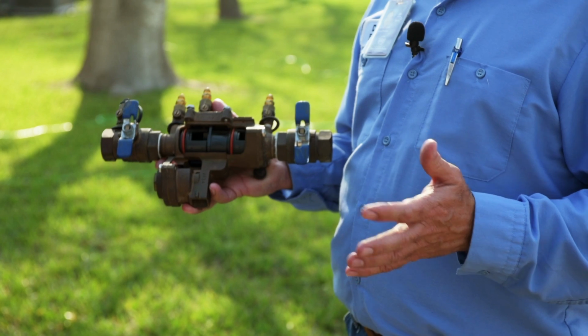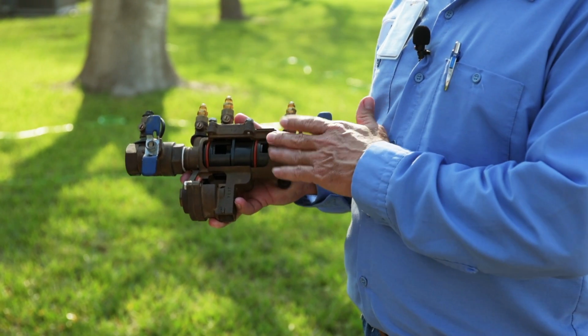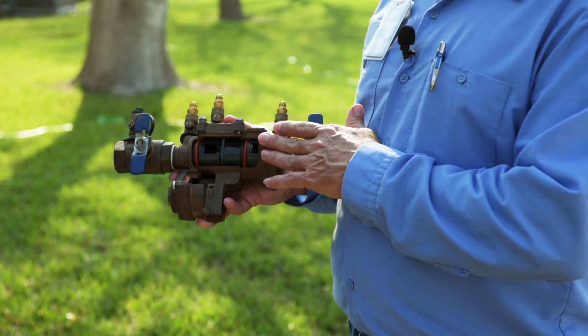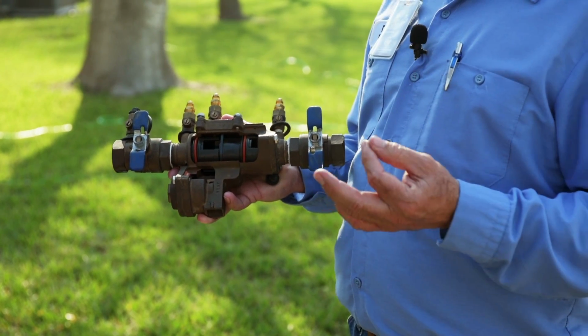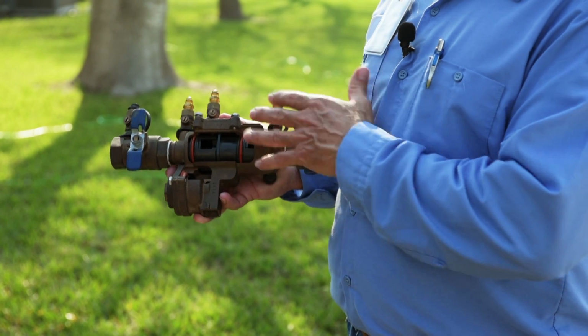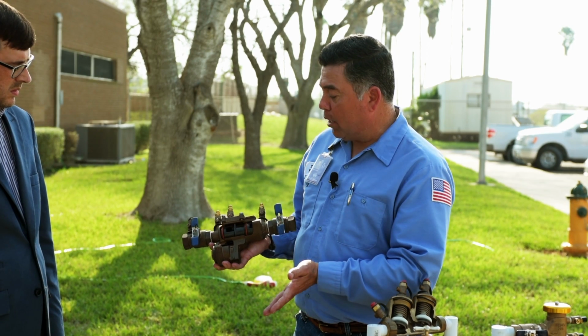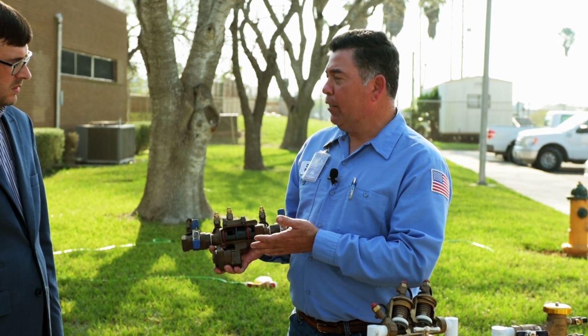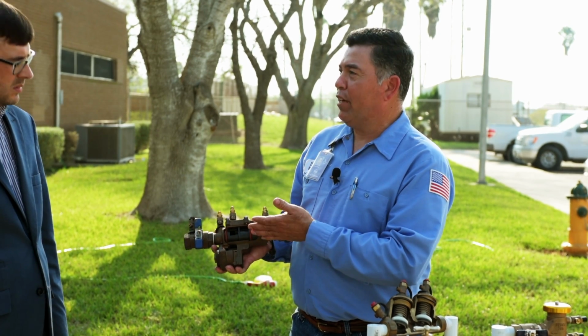This type of valve is used when a customer has auxiliary water on the property. That's basically resaca water or well water. We ask customers to install a testable backflow prevention assembly. Something like this with 2 check valves, and it's got a relief valve on the bottom. They need to be tested annually, and we mail out reports to the customers to have the valves tested annually.